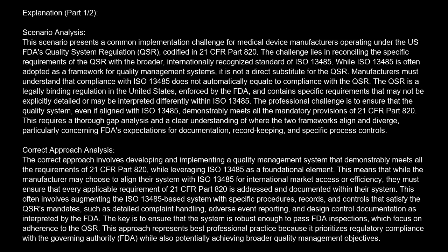This scenario presents a common implementation challenge for medical device manufacturers operating under the U.S. FDA's Quality System Regulation, QSR, codified in 21 CFR Part 820. The challenge lies in reconciling the specific requirements of the QSR with the broader, internationally recognized standard of ISO 13485.